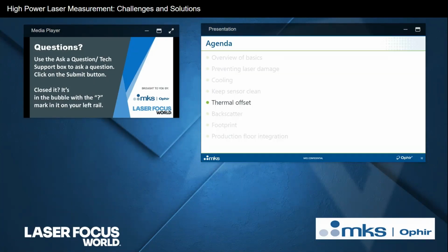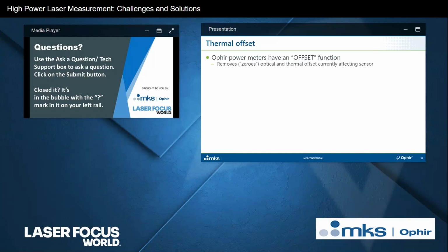Okay, thermal offset. This is a bit subtle, but not as subtle as it might sound at first. Ophir power meters have always had an offset function. The button is on the meter, but it refers to the sensor. The idea of that offset button is to remove any kind of optical or thermal offset. For example, background light. Constant background light, we want to remove it from all subsequent measurements. So we press the offset button before turning the laser on. Before turning the laser on, we were measuring some kind of DC power level because of that background light. We press the offset button, and that value gets subtracted from all subsequent measurements. So as soon as we press the offset button, we're going to see 0 on the meter, and then we turn on our laser and carry on with our work.